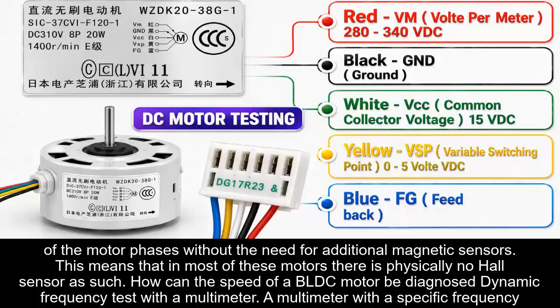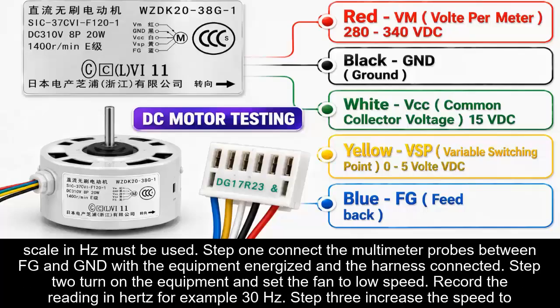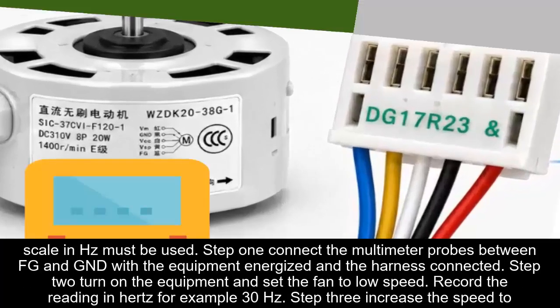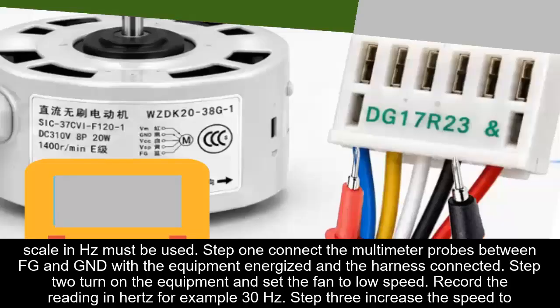How can the speed of a BLDC motor be diagnosed? Dynamic frequency test with a multimeter. A multimeter with a specific frequency scale in Hertz must be used. Step 1. Connect the multimeter probes between FG and GND with the equipment energized and the harness connected. Step 2. Turn on the equipment and set the fan to low speed. Record the reading in Hertz, for example, 30 Hertz.